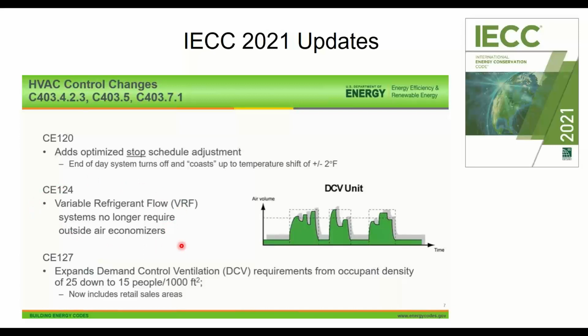The way it is today, if you put a VRF system in a commercial building, you still have to follow the rules for putting an economizer in. You don't get a pass on that. Now, most of you that have done VRF know that putting an airside economizer in a VRF doesn't really make any sense because you don't have any ductwork. So how are you supposed to bring in outside air more than the code outside air to get free cooling? It's not a good match. So what you have to do today is either A, don't follow code and hope no one notices, right? And feel good about yourself because you put in a really efficient VRF and it kind of made up for it.